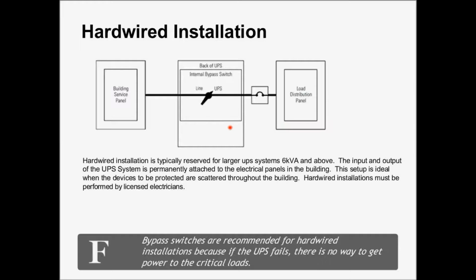One thing that you always want to make sure of is that you have a maintenance bypass switch, because if the UPS ever fails, you need to be able to get power to your equipment quickly. If you don't have that, you would have to call an electrician and have him come out and wire around the UPS. Whereas if you have the bypass switch, you just throw the switch and you immediately have power back to your equipment. If you have equipment or computers that are spread all over the building, hardwired is definitely the way to go. It does have to be done by a licensed electrician.